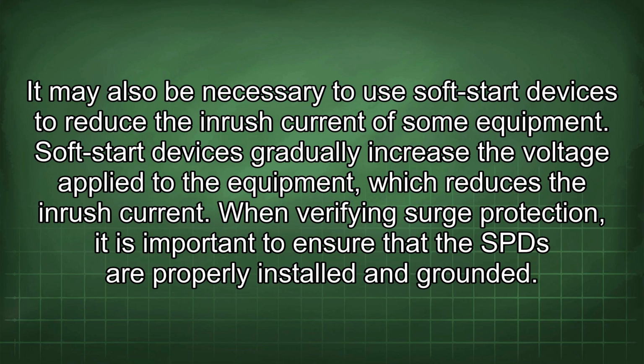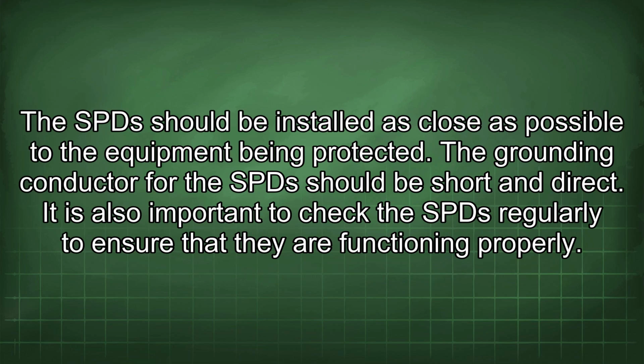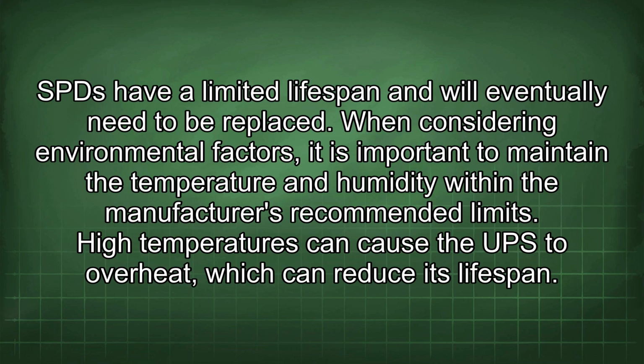When verifying surge protection, it is important to ensure that the SPD are properly installed and grounded. The SPD should be installed as close as possible to the equipment being protected. The grounding conductor for the SPD should be short and direct. It is also important to check the SPD regularly to ensure that they are functioning properly. SPD have a limited lifespan and will eventually need to be replaced.